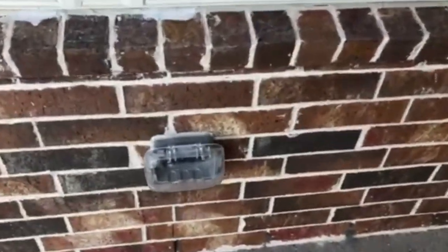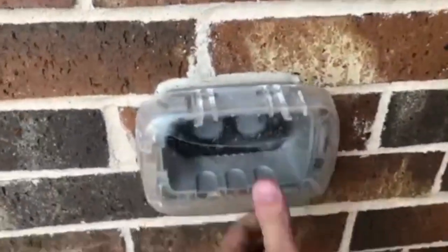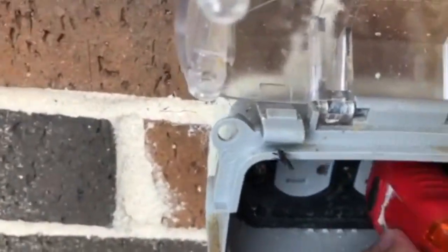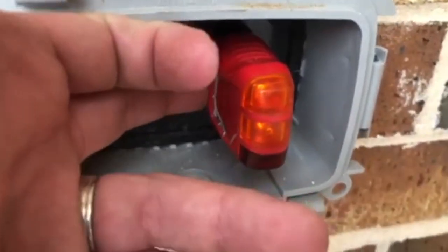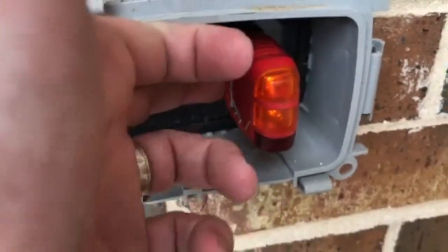They do have the weather cover, which is good. Opening this up and plugging in my outlet tester — we can see the outlet is working, it's got the lights on. When I press this button on my outlet tester, it's supposed to turn the outlet off.